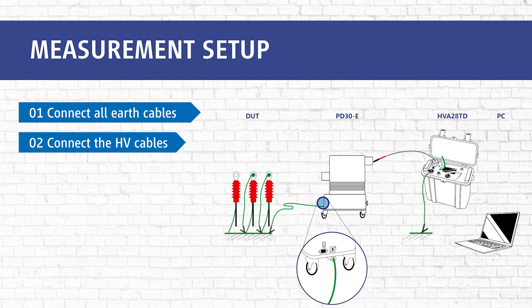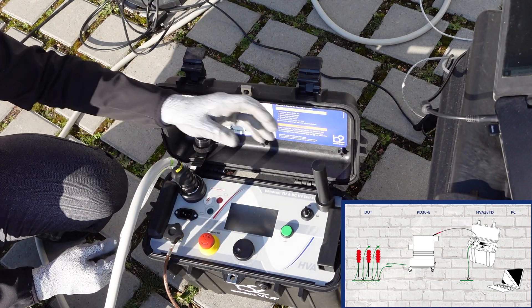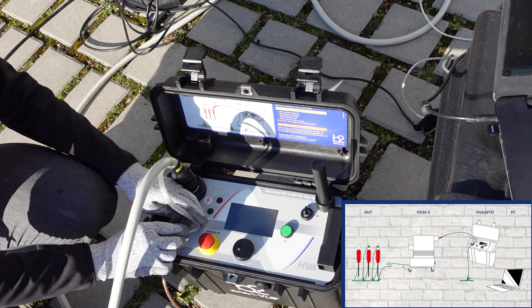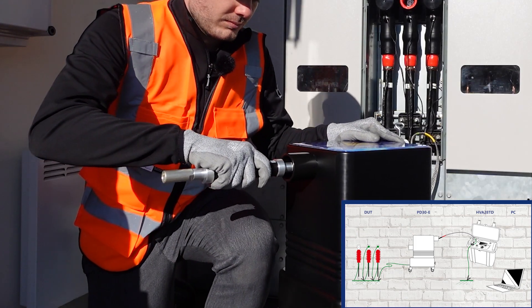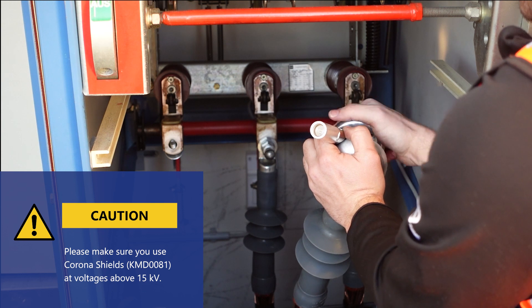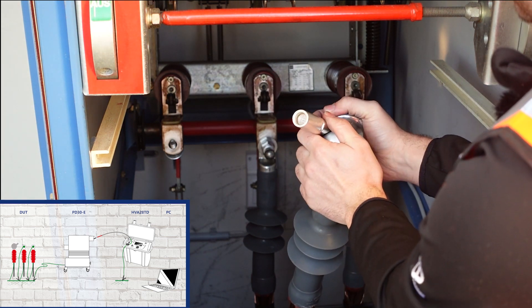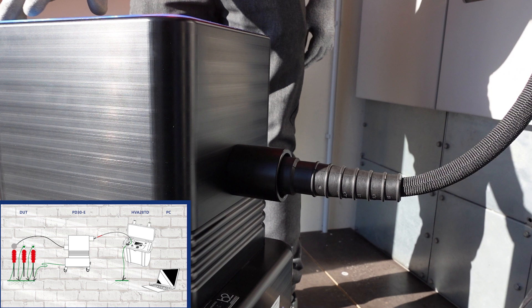In step two we connect all HV cables — first between the HVA and the PD30E. Then we connect the HV test lead to the PD system; we recommend using the impedance from the accessory kit. For voltages above 15 kV we recommend the use of corona shields. Between the PD30E and the DUT, please make sure to keep the connection as short as possible.